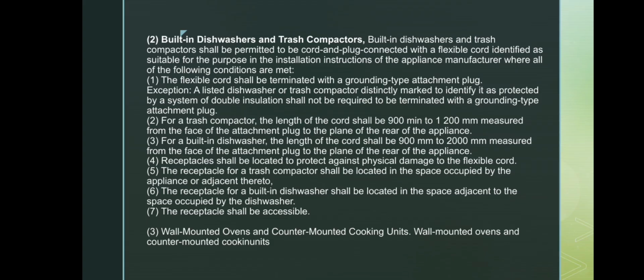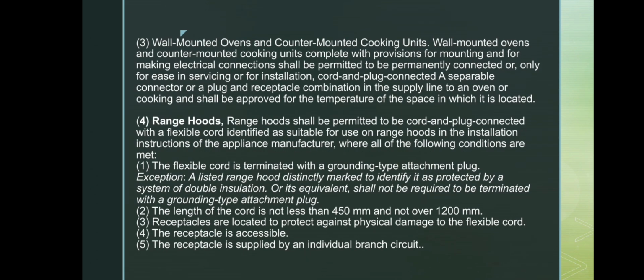Wall mounted ovens and counter mounted cooking units may be permanently connected or cord and plug connected for easier servicing, but the plug and connector must be rated for the temperature of the installation area. In this slide, we tackle wall-mounted ovens and counter-mounted cooking units. They can be permanently connected, or they may use a cord and plug connection only to make installation and servicing easier.